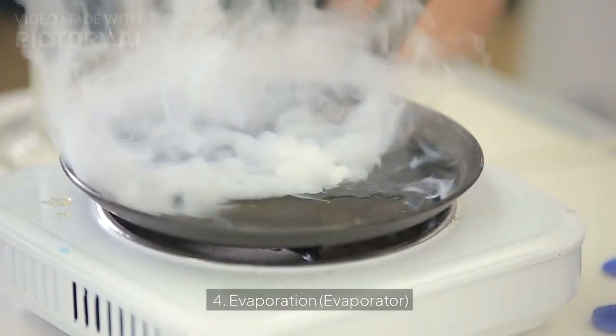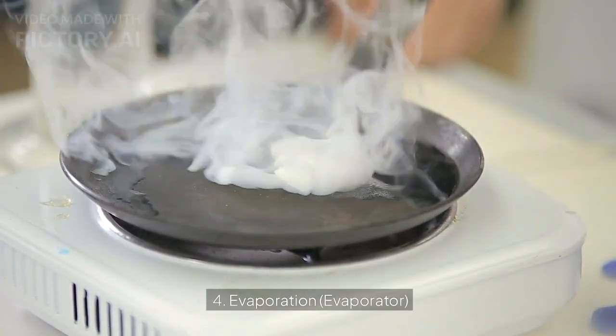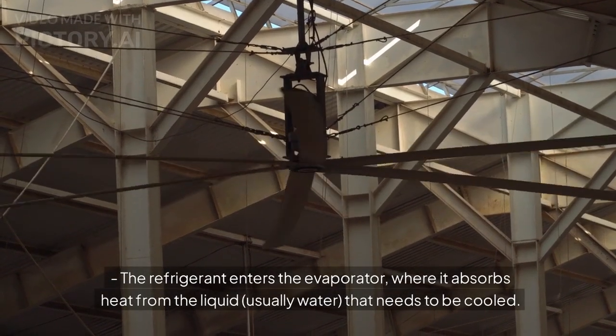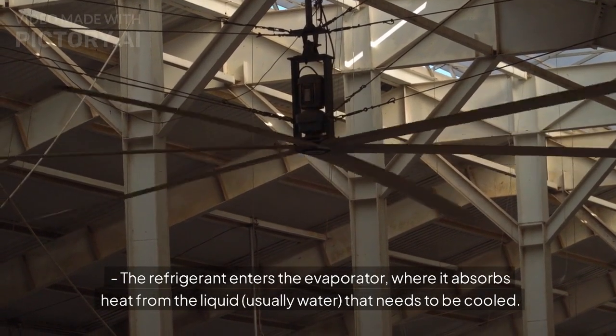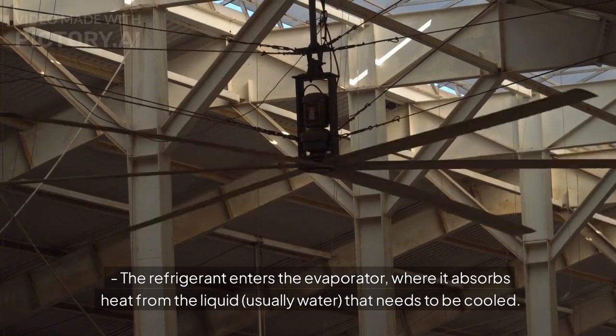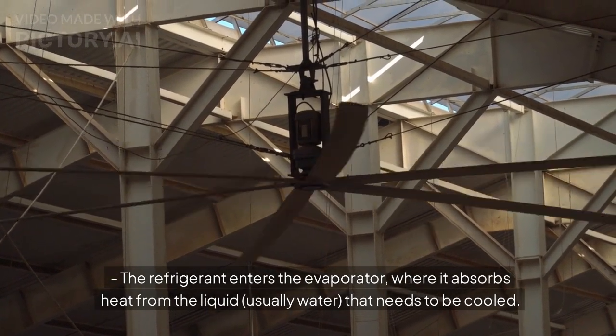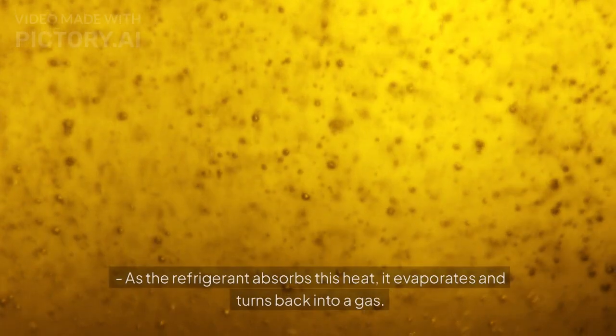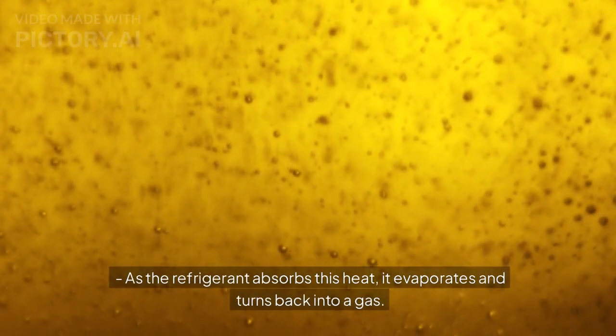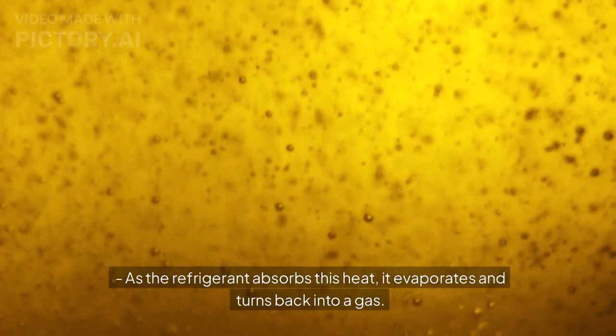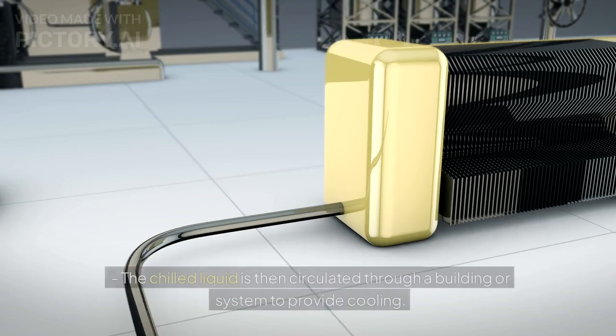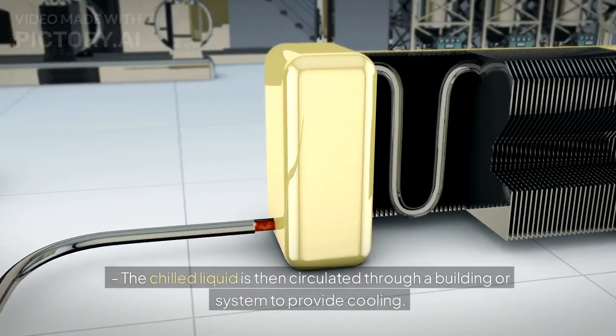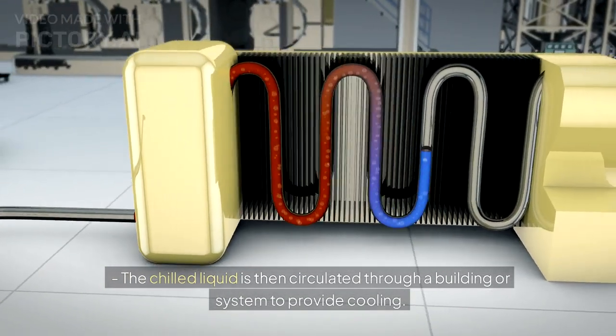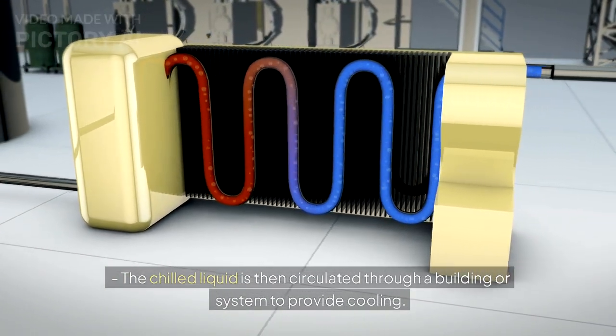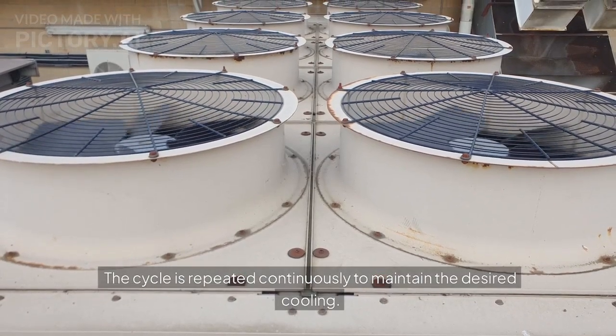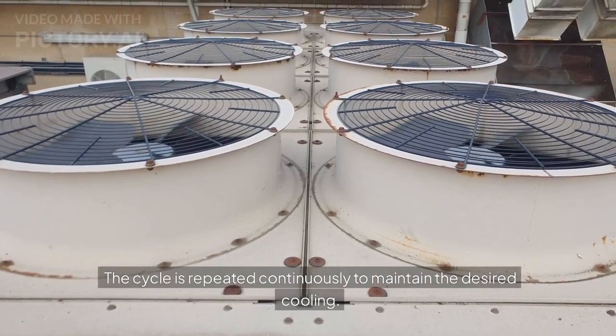4. Evaporation. Evaporator. The refrigerant enters the evaporator, where it absorbs heat from the liquid, usually water, that needs to be cooled. As the refrigerant absorbs this heat, it evaporates and turns back into a gas. The chilled liquid is then circulated through a building or system to provide cooling. The cycle is repeated continuously to maintain the desired cooling.